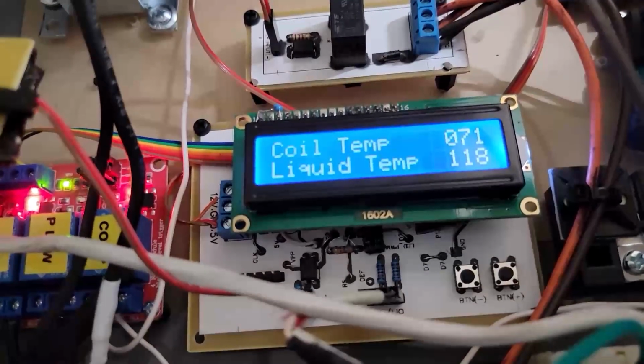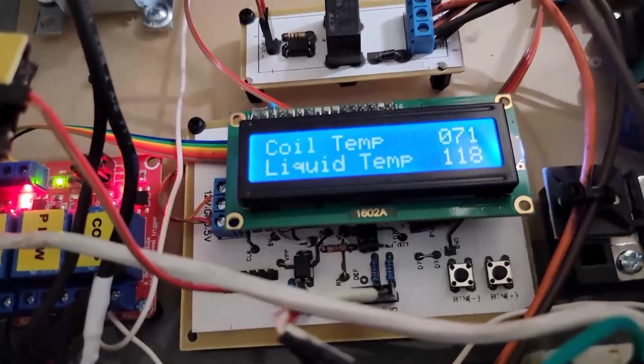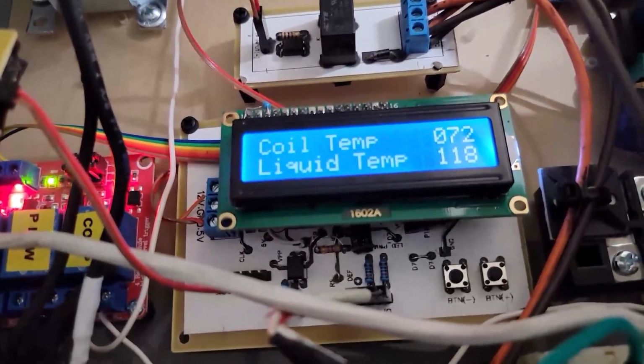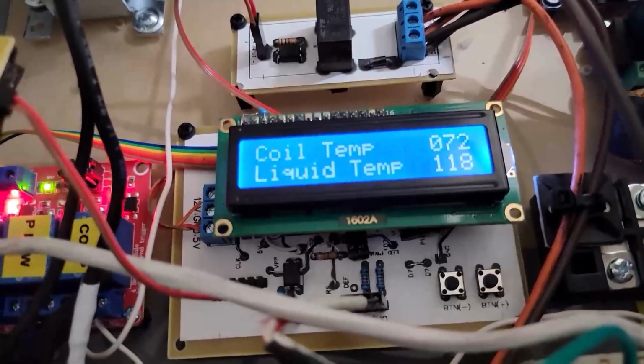Oh, 71 degrees. I forgot I moved that probe over on the suction line right there, 71. We'll go see how accurate that is. 72, 71, 118 liquid line. Yeah, the liquid line's way above the high speed set point because it's hot out there. I wonder what that would have said earlier before I put the misters on.